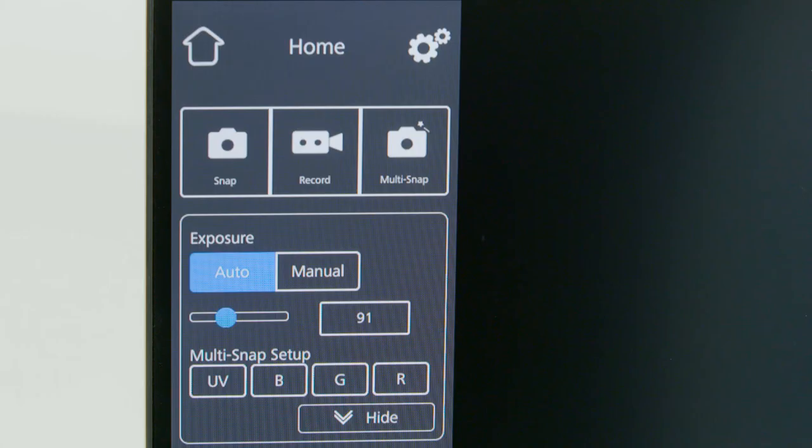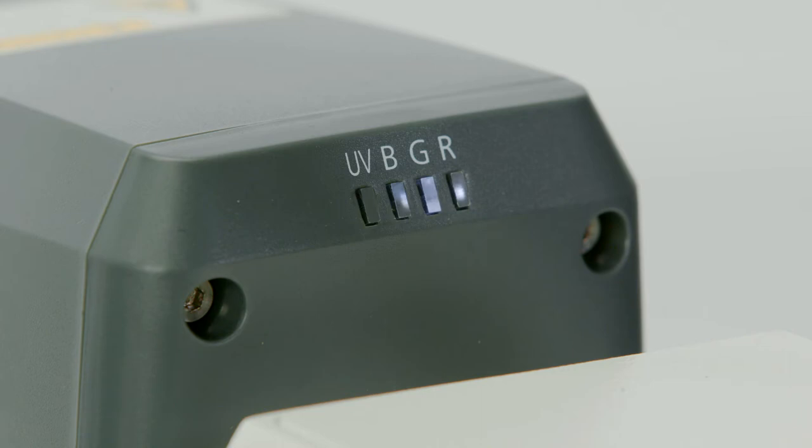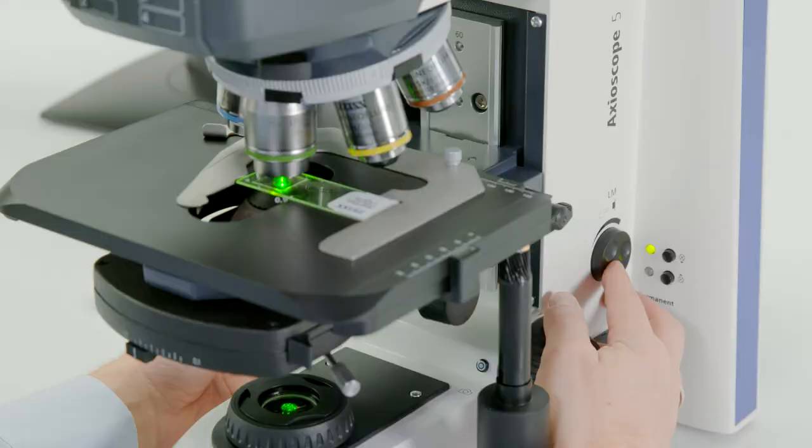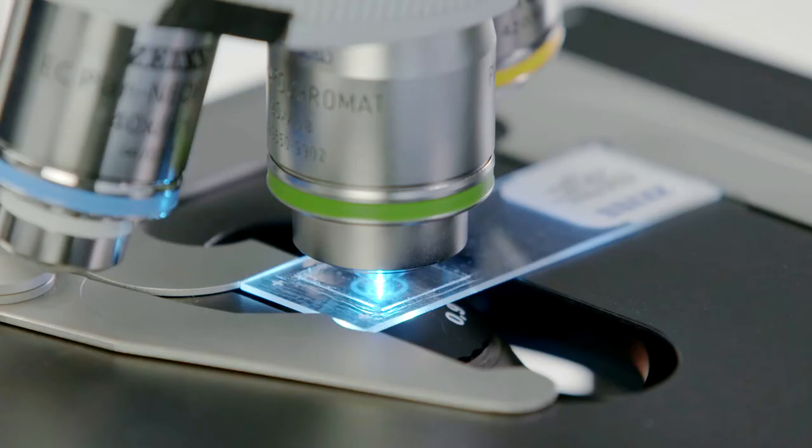Now you're ready to switch to the fluorescence mode on your Axioscope 5 microscope. Toggle to the UV LED. Since DAPI provides a strong fluorescent signal, use a low magnification objective to locate and focus your sample, then switch to the magnification you need.